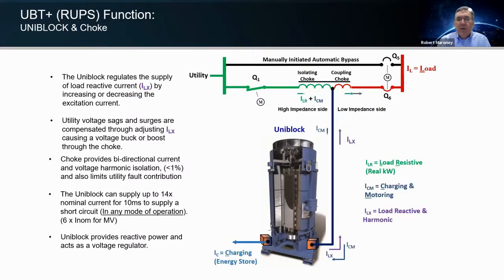There we go. I was missing a part of my slide. If we see a voltage dip, we're going to monitor that, and we're going to increase excitation of the uniblock to deliver reactive power through the coupling choke to the load to provide the output waveform. If we see a spike, we're actually going to reduce excitation and absorb VARs into the uniblock motor generator to hold output power and waveform nominal.